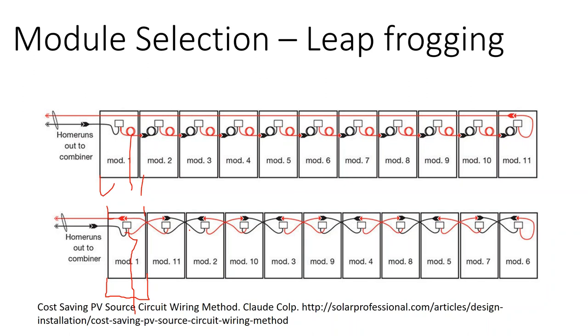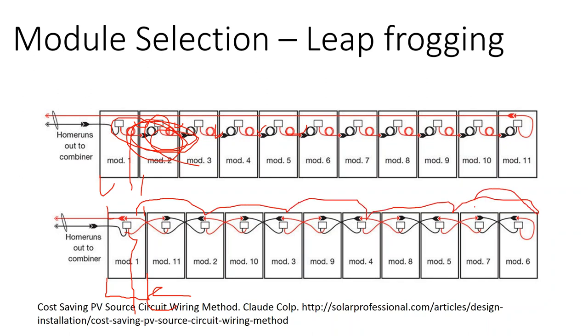And in the utility scale arena, they've realized that, hey, if I'm up on the rooftop, I'm clicking my modules together, usually like this, positive, negative, and I get all this extra cable that I'm not really using, just kind of bundled up together. Whereas if I'm on the ground and I'm using 72-cell modules, I have enough cable length that instead of plugging into my next door neighbor, I'm going every other module and then all the way back.